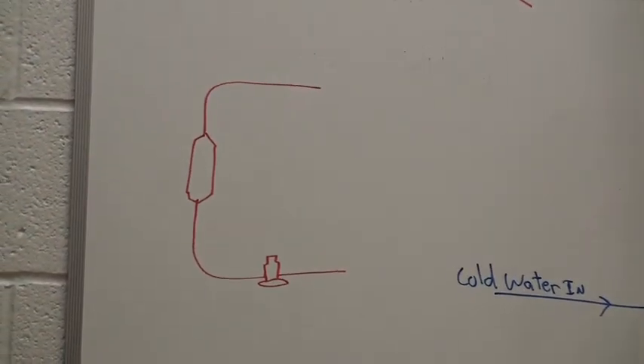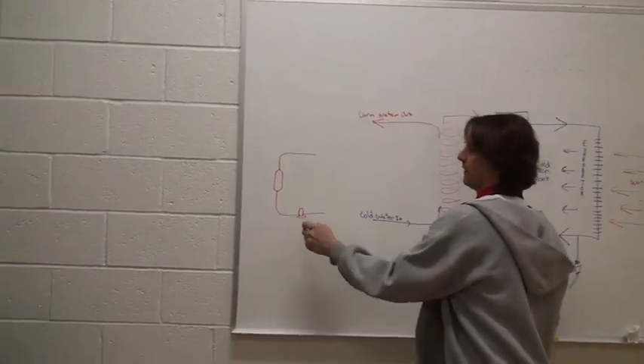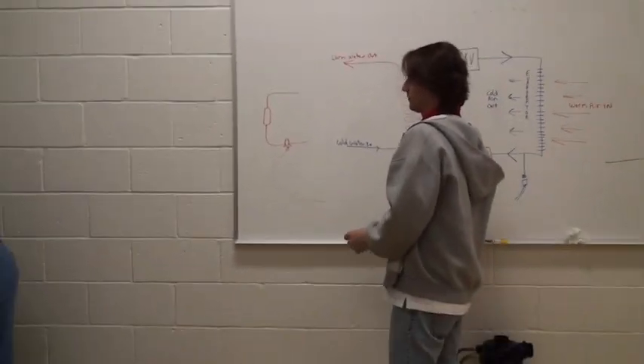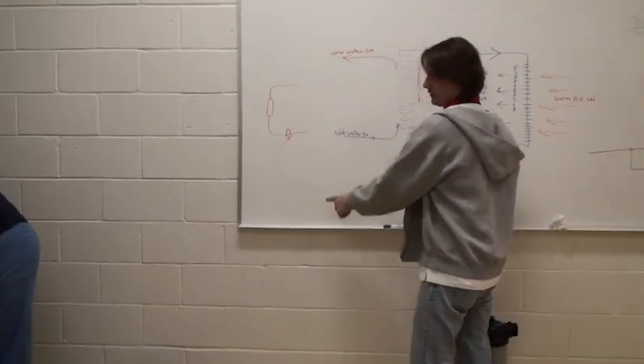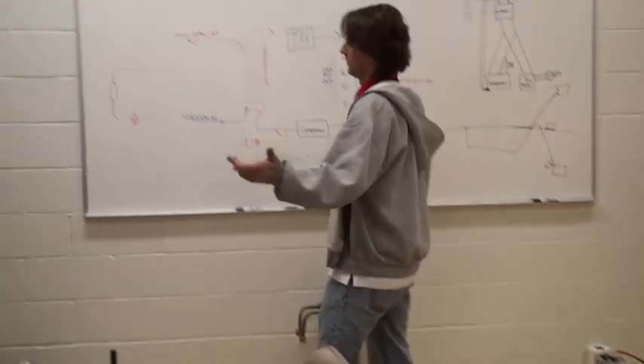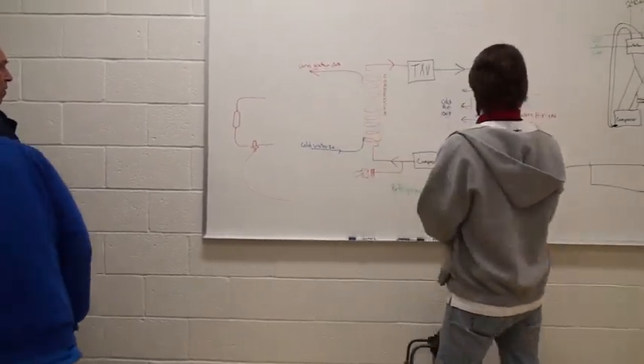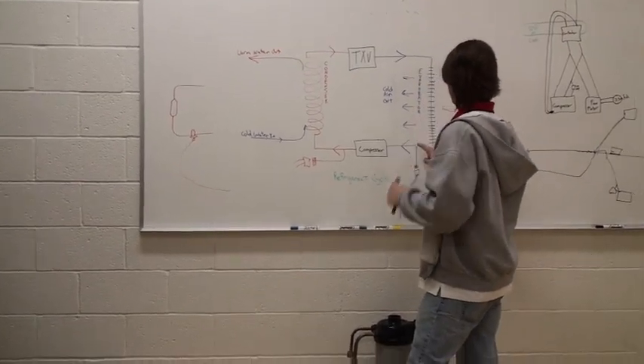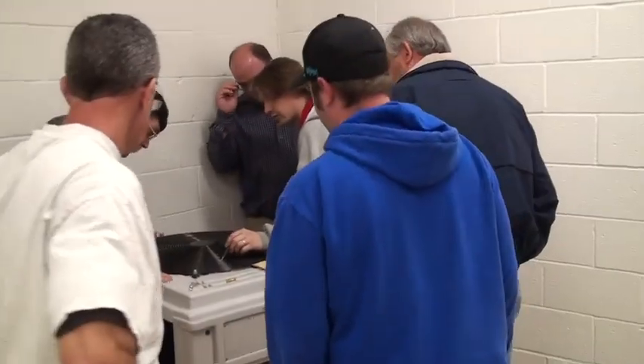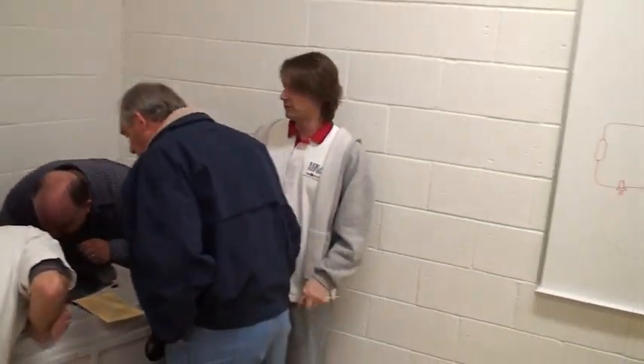Yeah, it's that thing right there at the bottom. What are the wires coming off? There's a capillary line that comes off the bottom of it, and that capillary line is just like this—the liquid-filled bulb. It's just like the thermostat, full of refrigerant. And it's attached to the line right here, which is vapor return. You'll see cork tape on that large copper line. That cork tape is covering that bulb to insulate it.